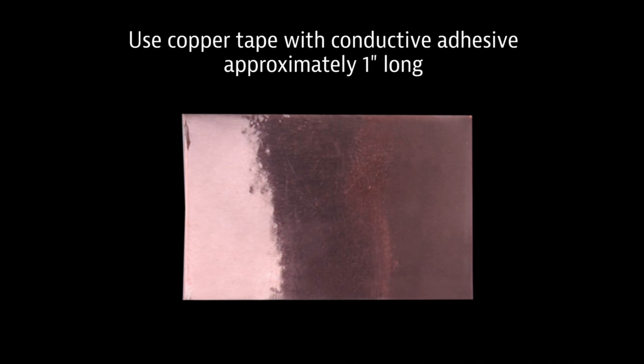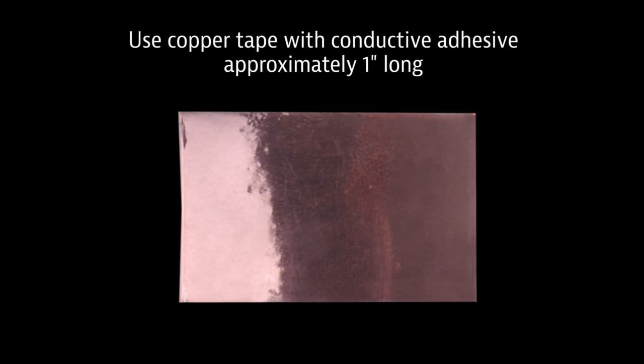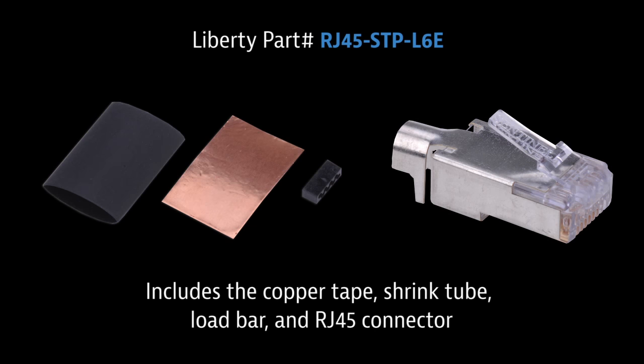For the best practices application, you want to secure your drain wire with copper tape. You don't want to use just any copper tape - you want to use copper tape that has a conductive adhesive. Liberty part number RJ45-STP-L6E provides you with everything you need for this termination.